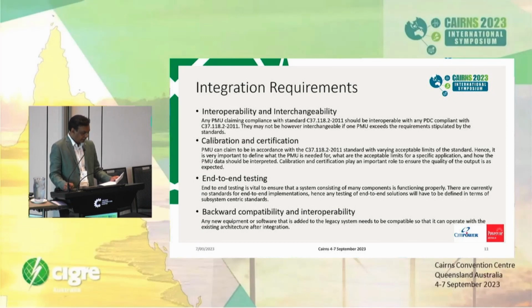PMUs claiming to comply to a standard can have variable acceptable limits, such as complying only for P class or M class, complying only at certain frames per second. Hence, it is important to get PMUs calibrated and certified based on specific requirements. We have already seen the benefit of end-to-end testing due to non-availability of standards. Solutions will have to be defined in terms of subsystem-centric standards. Backward compatibility is also important to enable new devices to work with the existing systems.